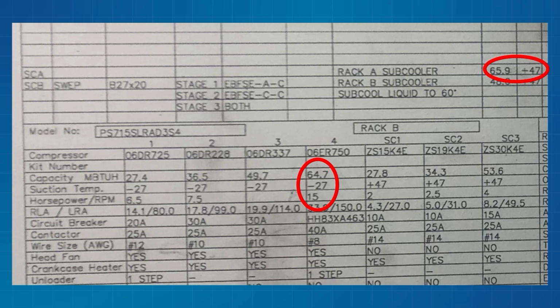Okay, so all that's fine and good. Oh, what do we got here? On this side I've got these are my satellite compressors for my subcooler. That's what I'm saying, having it all on one page makes this really easy. If I look at compressor 1 and compressor 2, these are their MBTUs. I add those together, they're not exactly the same, but they are really close to the same load as that: 61, 58, 62. So 62, pretty close to 64.